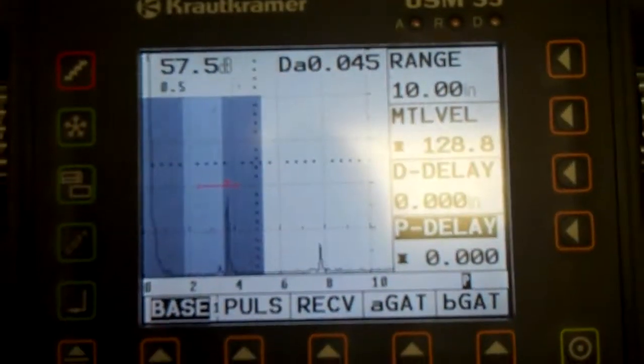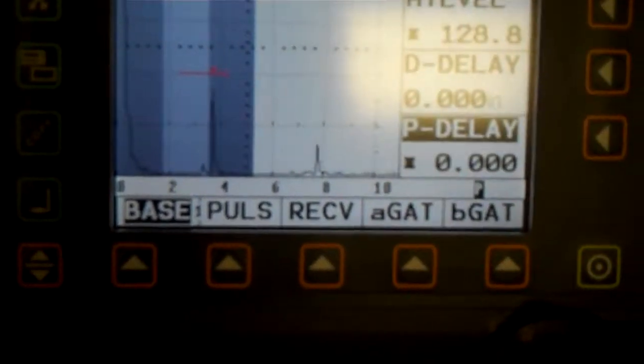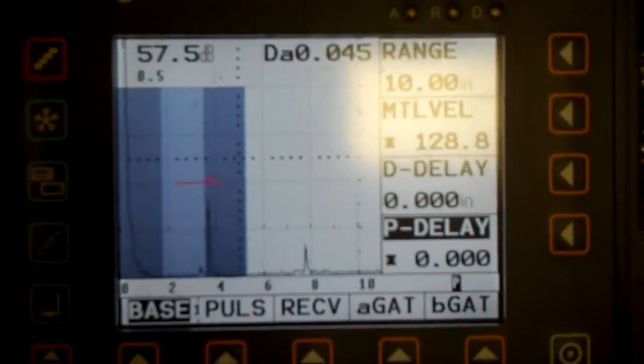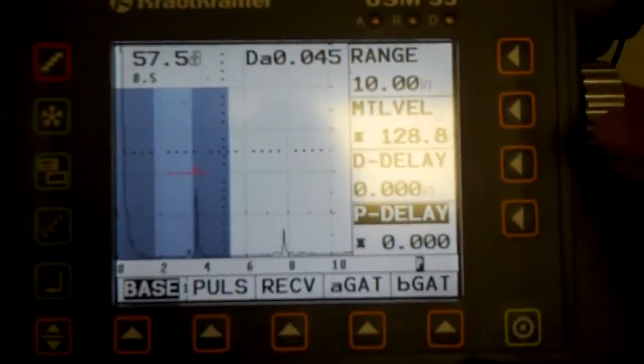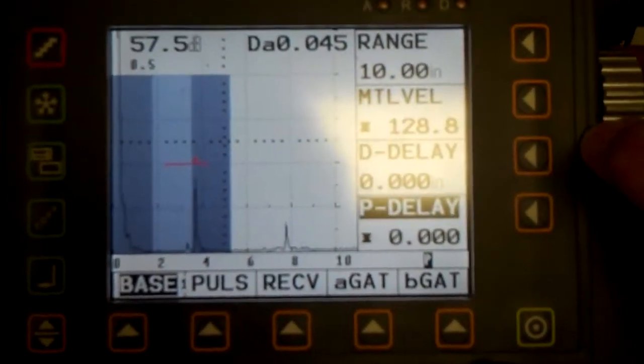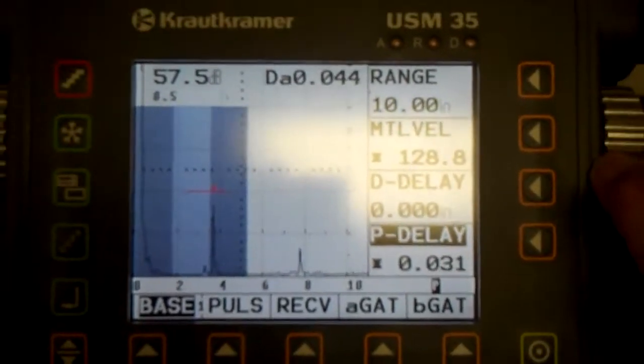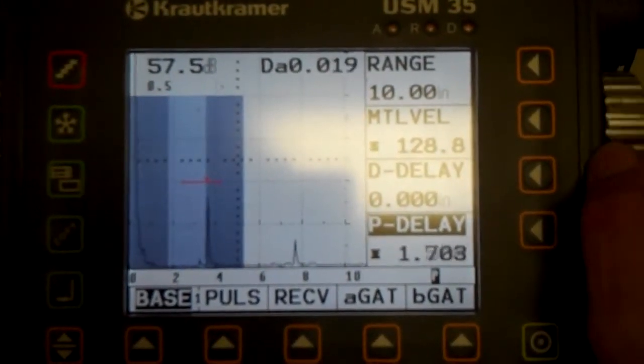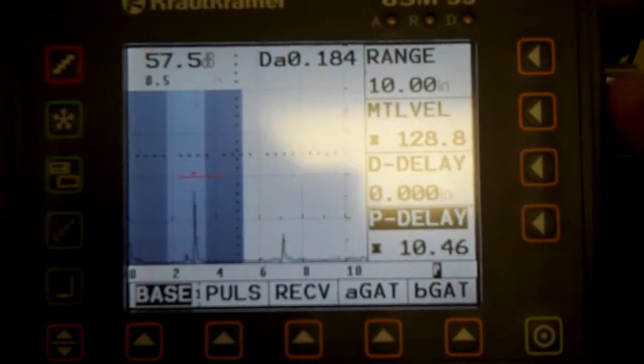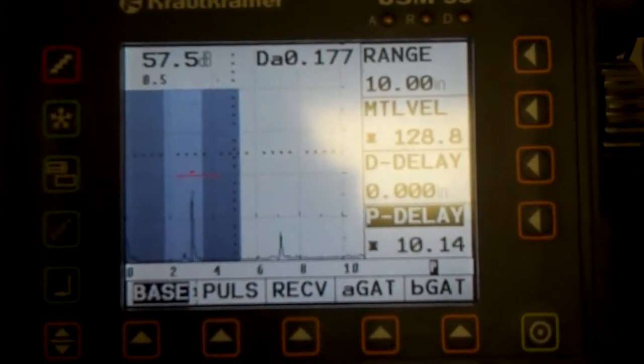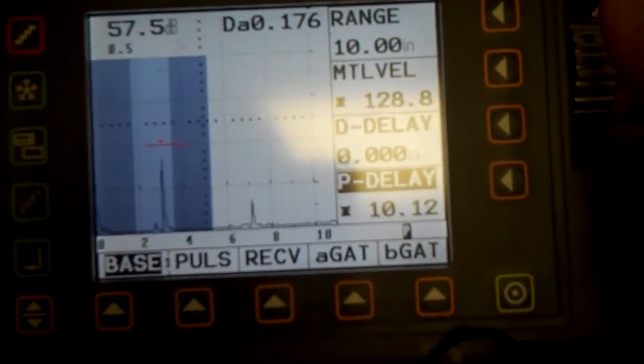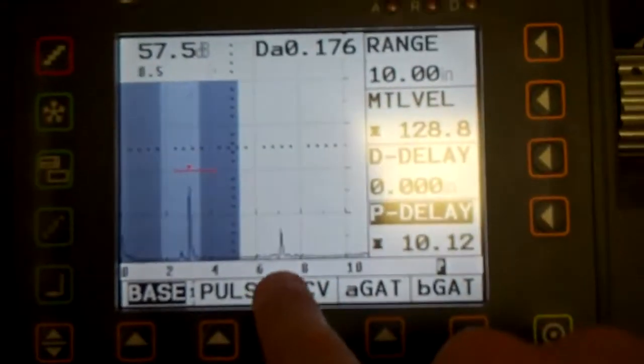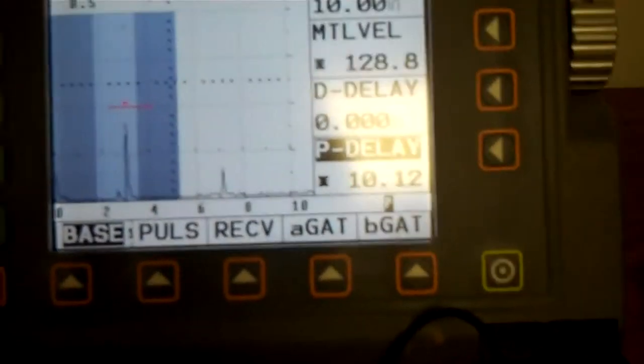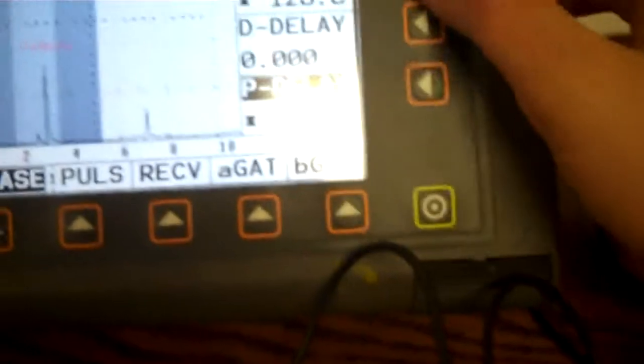That signal right there has generated these signals right here. So, first thing I need to do is I need to get that to 3 and 7. I'm going to do that by moving my probe delay. So first signal I'm going to set at 3 inches just by moving my probe delay. Okay? So I've increased my probe delay. I'm at 3 inches, and just out of pretty good luck, it looks like I'm right at about 7 inches, but for fun, I'm going to squeeze that in just a little bit more.